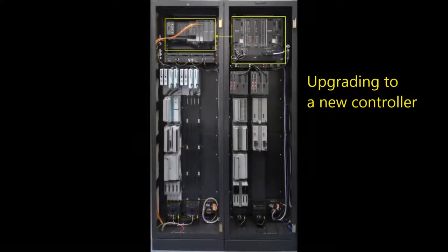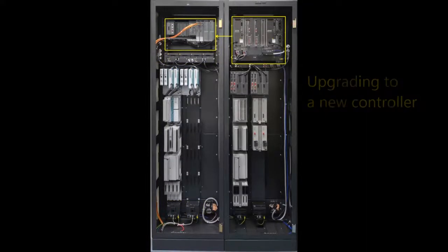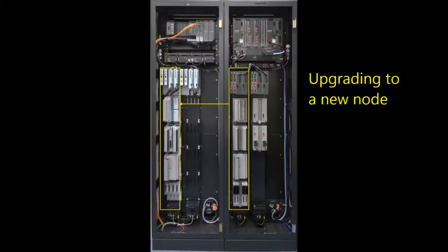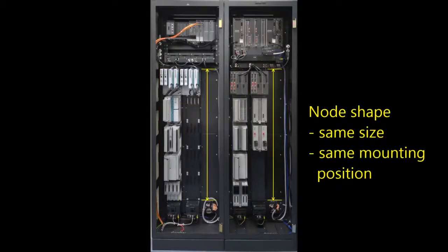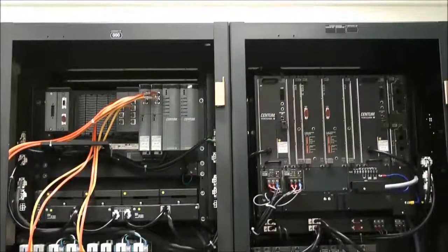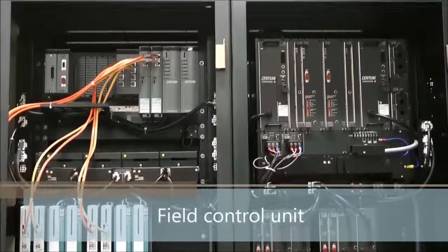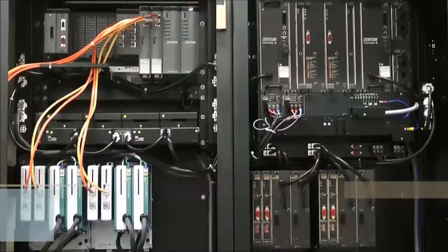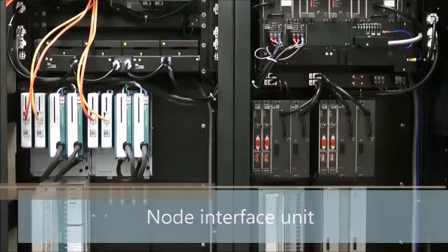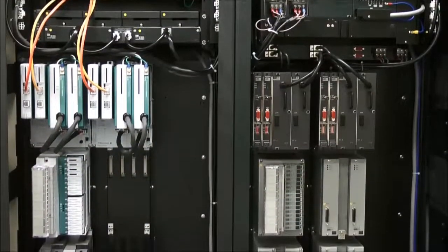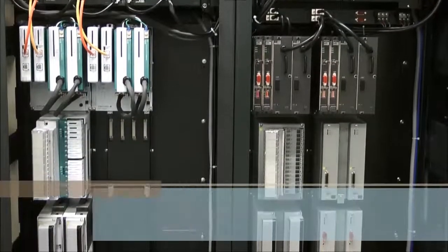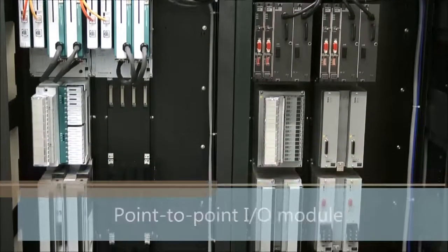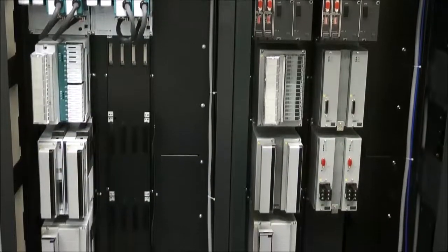The field control unit and I/O nodes will be replaced with new ones on a one-for-one basis. The I/O node is shaped to the same size and mounted at the same position. The field control units will be replaced with the latest upgrade version. The node interface units also will be replaced with new ones and connected with new I/O buses. The point-to-point I/Os, which are a feature of the RIO system, will also be replaced with point-to-point I/Os.